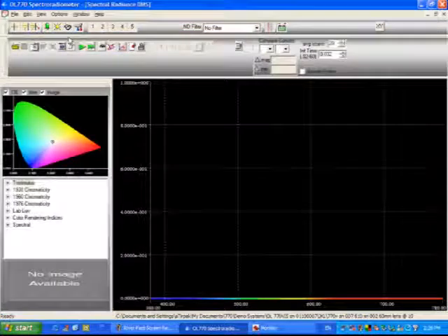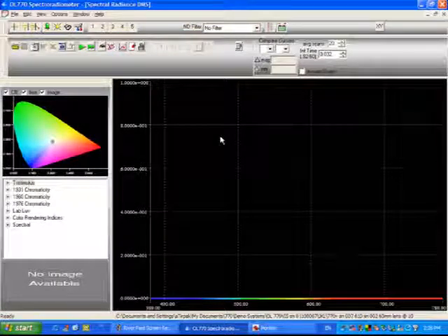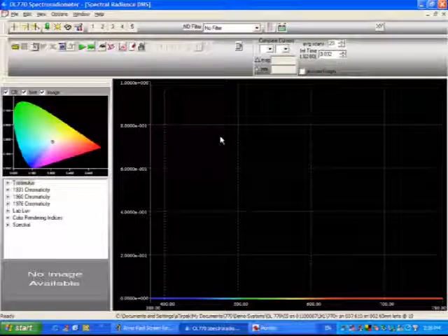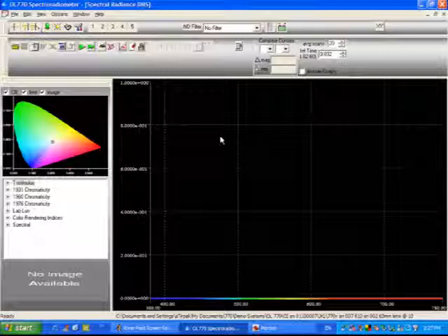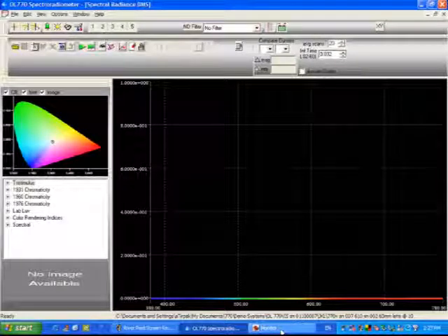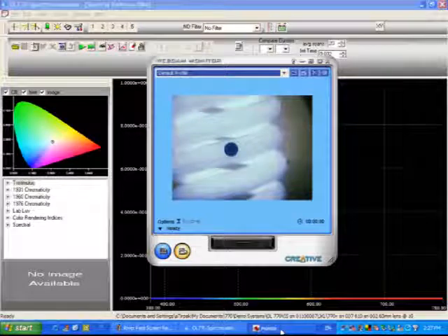Okay, now moving on to radiance. Locating the application software is as easy as we did before for the TLF and for the irradiance. We'd go to our source spectral tab, we would pull down to radiance, and we would get up our measurement screen again. Now, instead of doing a calibration and a measurement as we did in the past, those are identical to TLF and irradiance. I'd like to just concentrate on the alignment of the camera and what you would be seeing through the reflex telescope. Now, for convenience sake, we have another version of Pritchard-type optics design, an OL610 CCD imaging telescope, which allows us to view our alignment procedure by way of a CCD monitor.